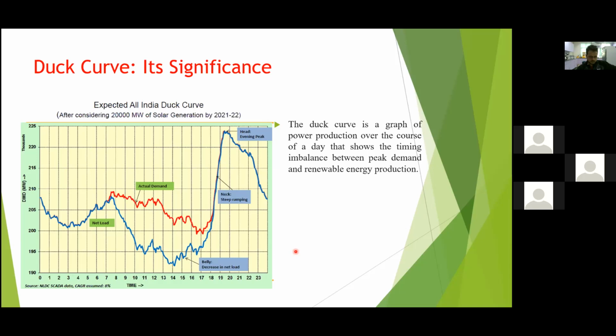So this duck curve is now a case study where you can see here that the ramp becomes very large, and it is difficult to handle this ramp by any grid, so that you may see the issue of getting a large ramp in the system.